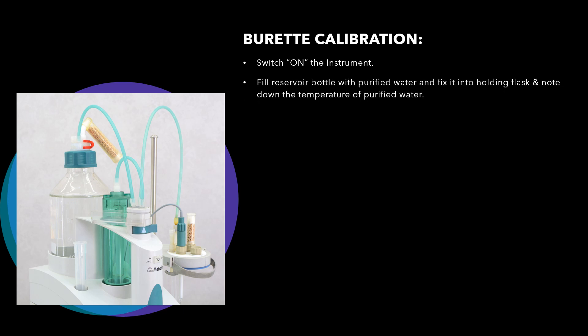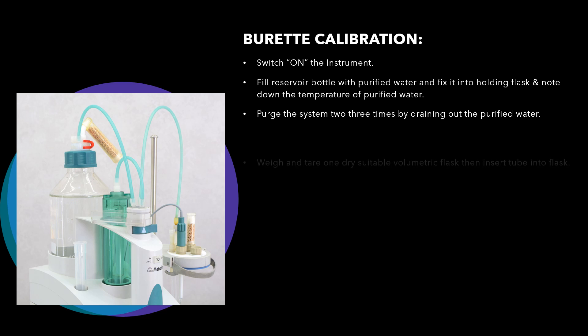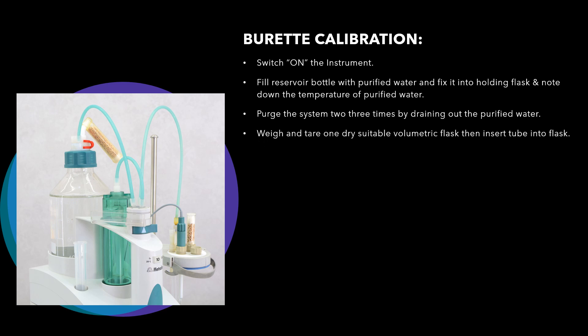Then fill the reservoir bottle with purified water and fix it into the holding flask, and note down the temperature of the purified water. To record the temperature you need a calibrated thermometer. With the help of that thermometer, take the temperature of the purified water. Then purge the system two to three times by draining out the purified water so that there are no air bubbles in the line.